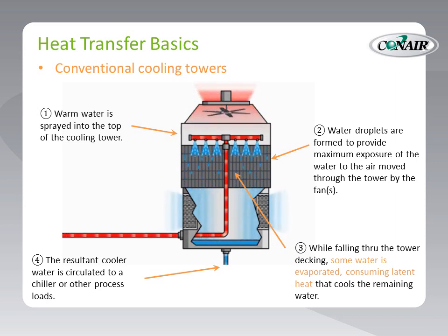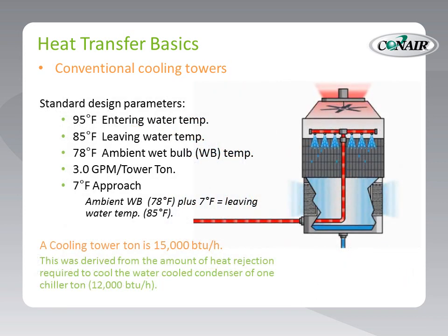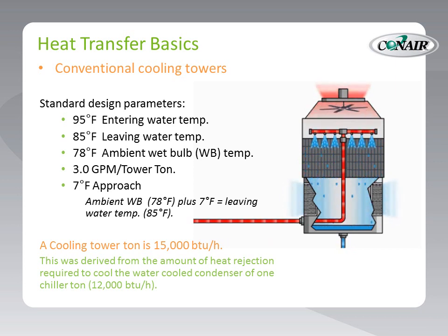The cooling tower capacity can be regulated by turning the fan or fans on and off, varying the volume of air flow through the tower as with a fan's variable frequency drive, or varying the volume of the water delivered to the tower as with a pump's variable frequency drive. The standard design conditions for an evaporative cooling tower are water enters at 95°F and leaves at 85°F with a 78° ambient wet bulb, while circulating 3 gallons per minute per cooling tower ton.